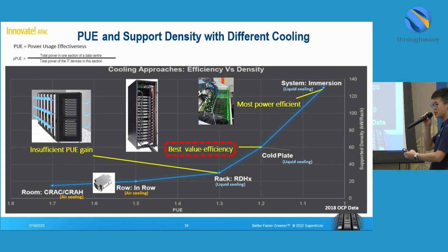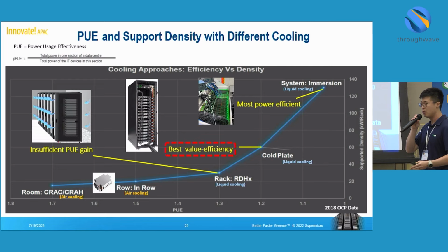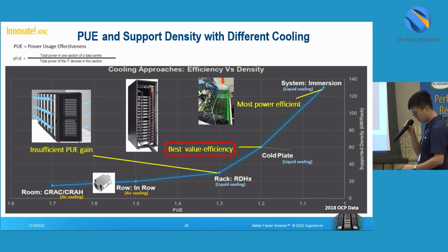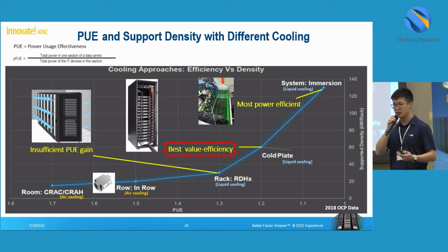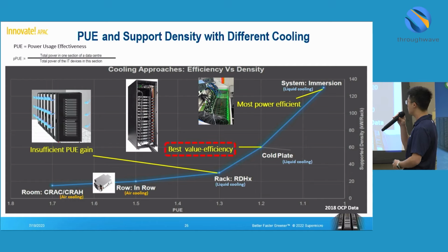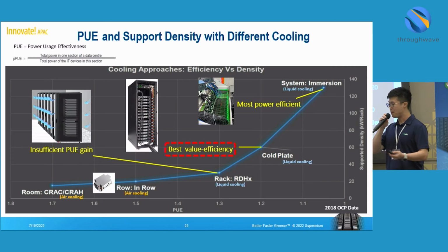This page shows the PUE and supported density per rack for different cooling solutions. As you can see, the rear door heat exchanger PUE is around 1.3, but it doesn't provide sufficient PUE gain over air cooling. The best value efficiency liquid cooling is cold plate, at around 1.2 PUE. And the most power efficient is immersion cooling. Today, I would like to focus on the best efficient cold plate liquid cooling solution in my presentation.